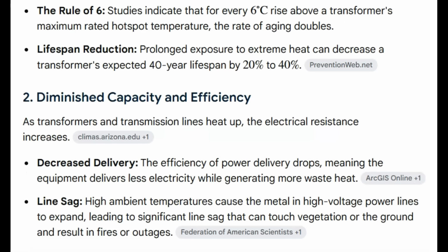And these power companies have what they call a rule of 6. Studies indicate that for every 6 degrees Celsius rise above a transformer's maximum rated hotspot temperature, the rate of aging doubles. They'll do it to your solar batteries too, unless you keep them inside, temperature controlled. That puts a 40-year lifespan on these transformers. It cuts it by 20 to 40% with extreme prolonged exposure to heat. Many are already at that 40-year lifespan.